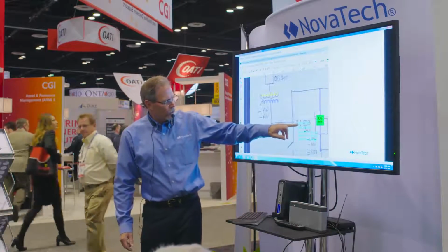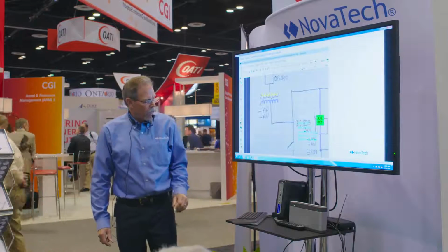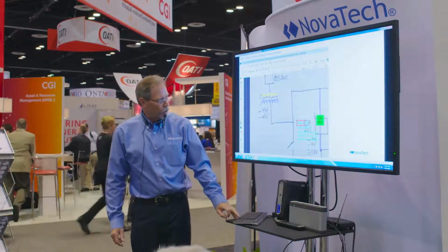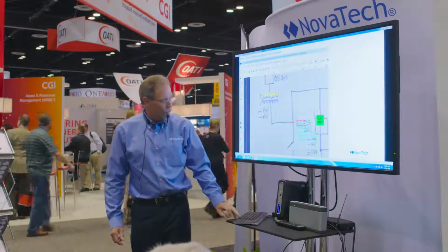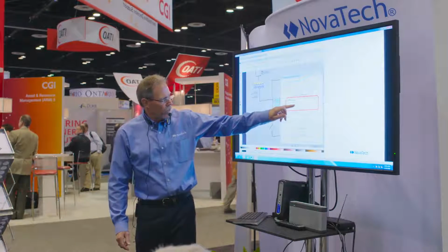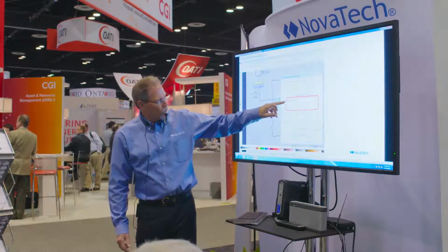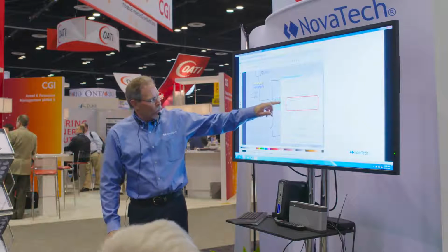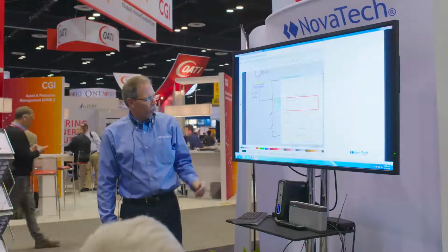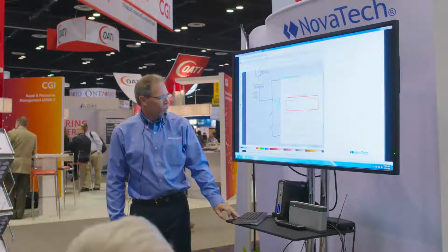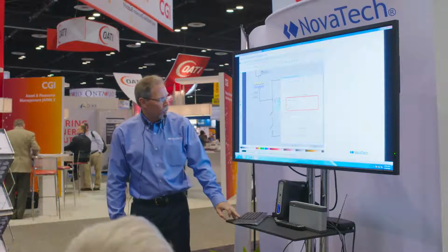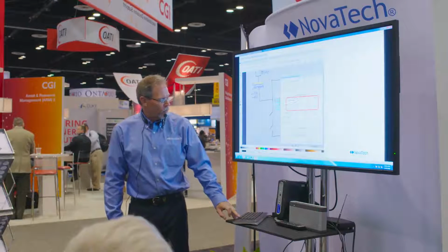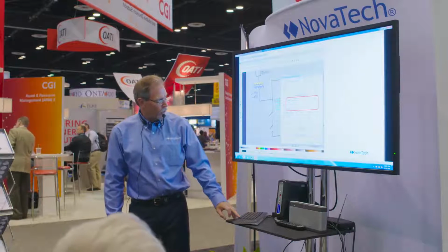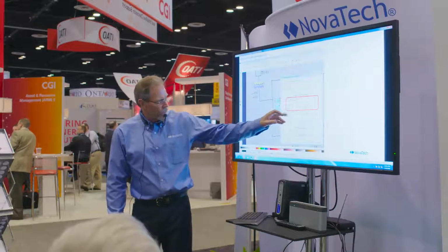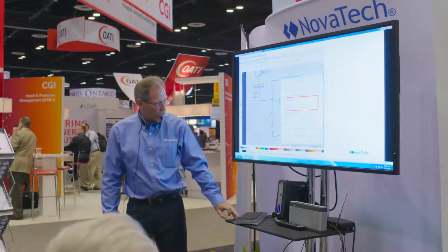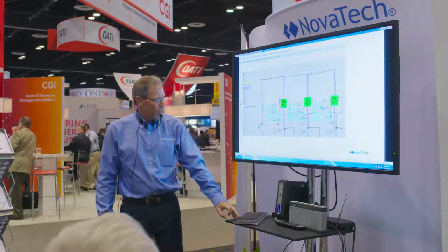The next thing I'm going to do is select the analog object and do the same thing — HMI extensions, pick a decimal value since it's now an analog. Where am I getting that analog value from in the XML database? In this case, it's coming from kilowatt readings from feeder 1 from the 751. I define how many decimal places I want that value to show, and I'm done.